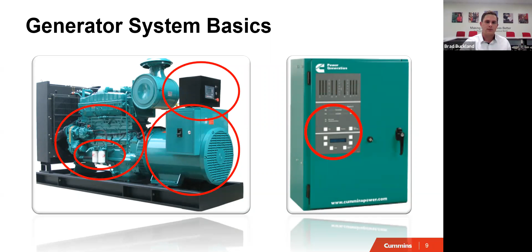So you have utility power coming in all the time, unless it's the middle of February in Dallas and everything shuts down. But once you get into it, the utility power and the generator are both running into this ATS, so it's sensing it all at once. It's sensing if there's any loss of utility power, and it's going to tell the generator to turn on at least, as a safety precaution, if that utility power is lost. And this is all happening within seconds.